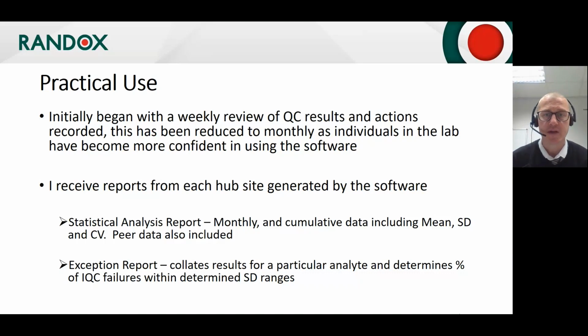So I receive reports from each hub site, which is generated by the program. The main report I receive is the statistical analysis report. This provides monthly and cumulative data, including mean, SD, and CV, and peer data is also included, which again can help if you've got a problem with a particular analyzer. It's easy then to determine whether it is just one individual analyzer or whether it's every analyzer that you've got across your network, whether the problems are appearing across it all.